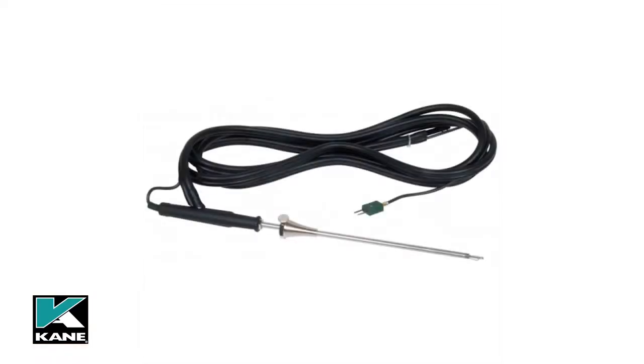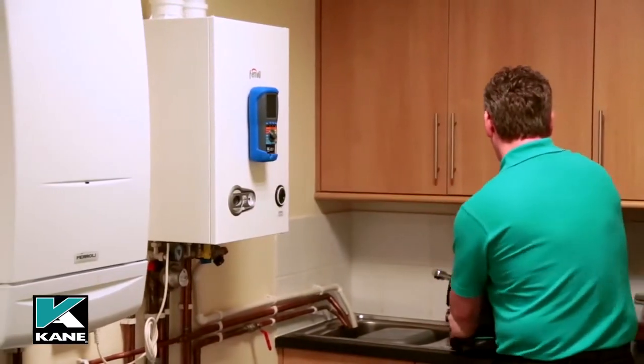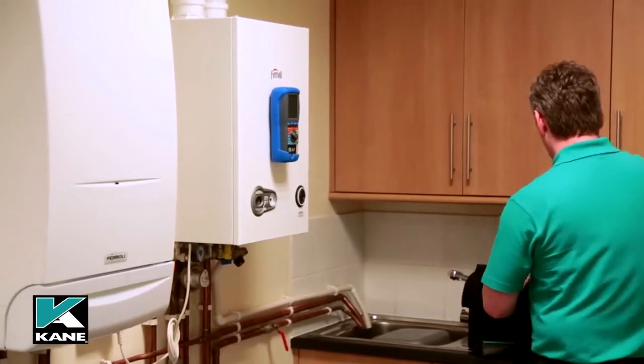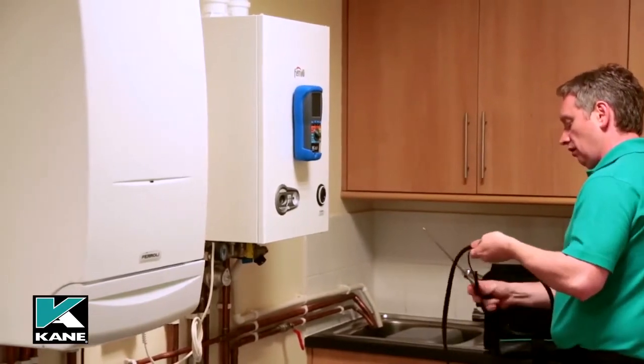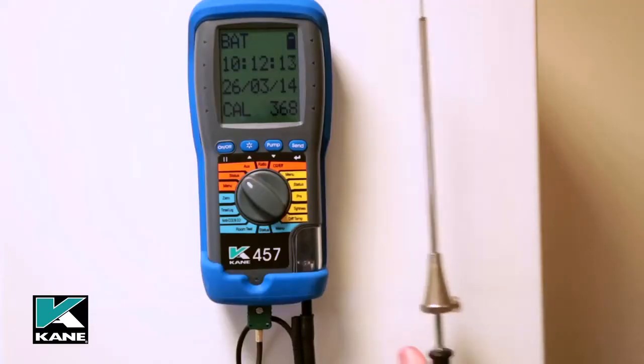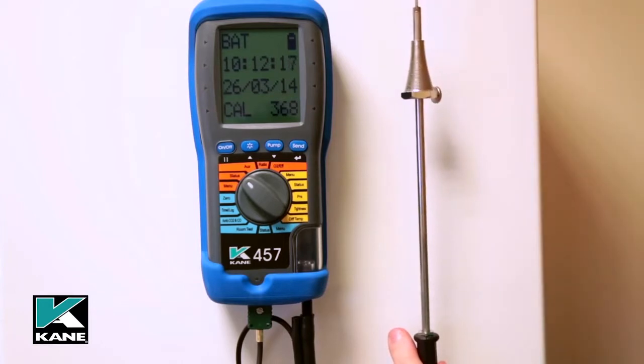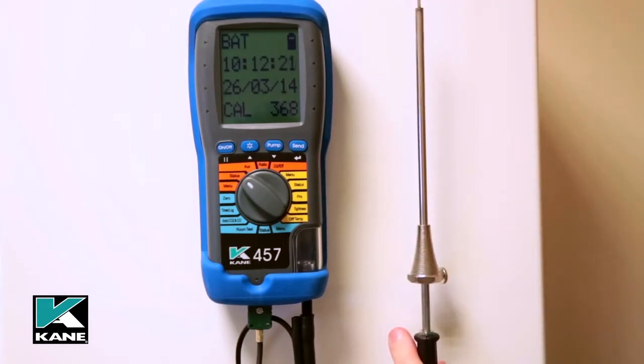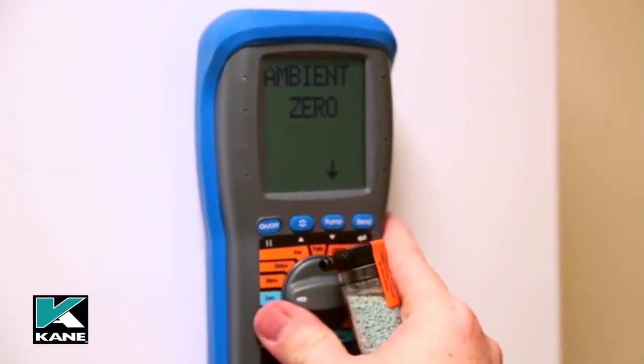The flue probe is an important part of the analyzer and is manufactured to a high specification. The 3-metre hose and stainless steel probe incorporates a thermocouple temperature probe providing accurate flue gas temperature measurement. The adjustable depth stop cone ensures accurate positioning into the flue. There is also an inlet for the CO2 zero calibration capsule, and we will go into more details of how this is used later.